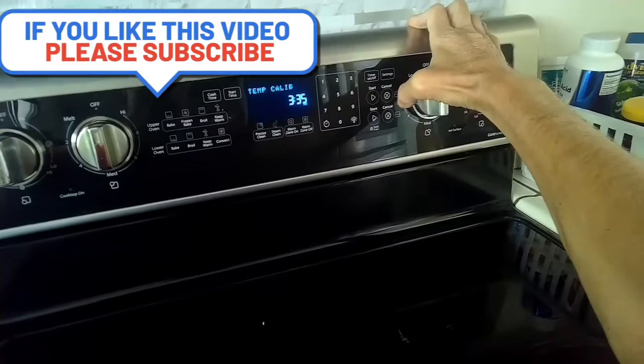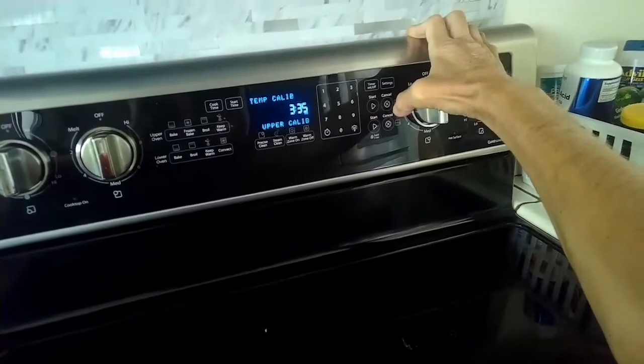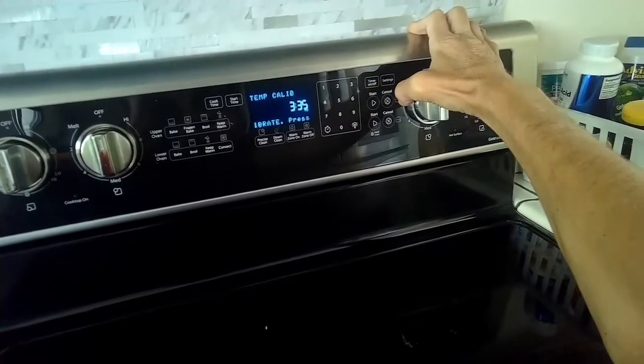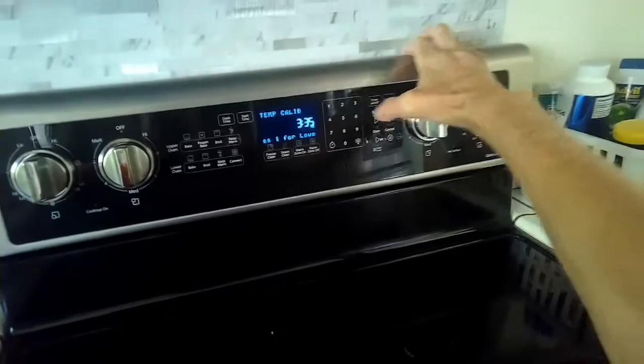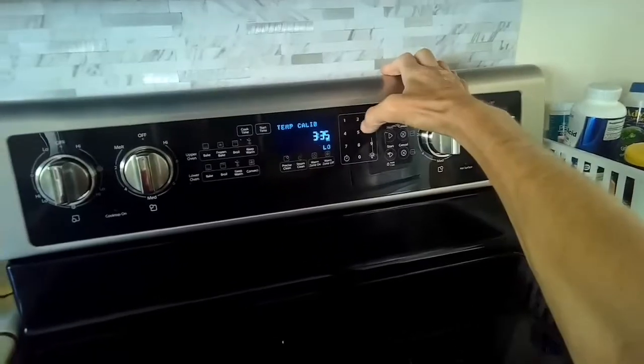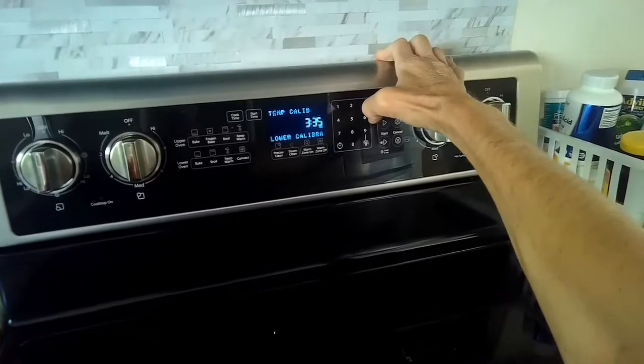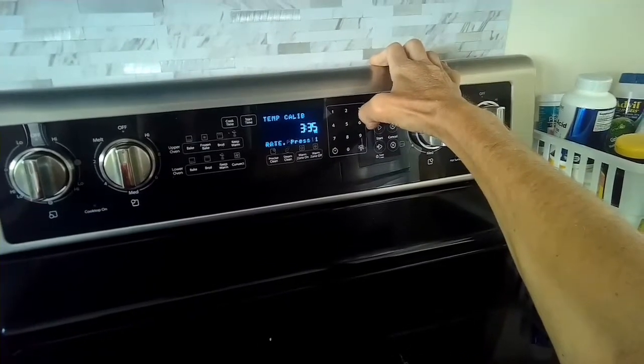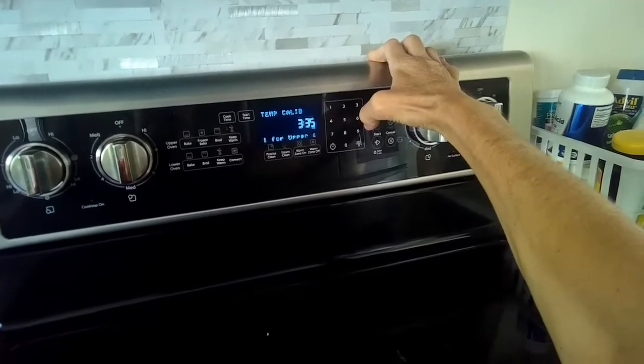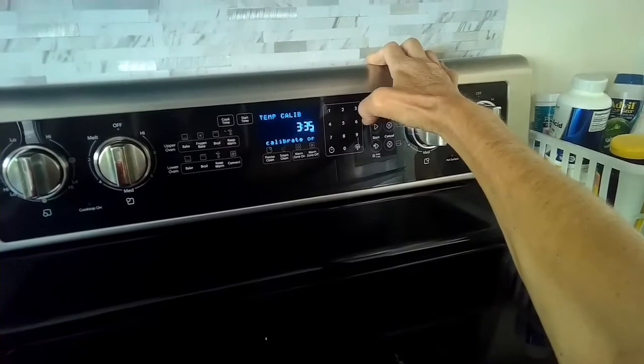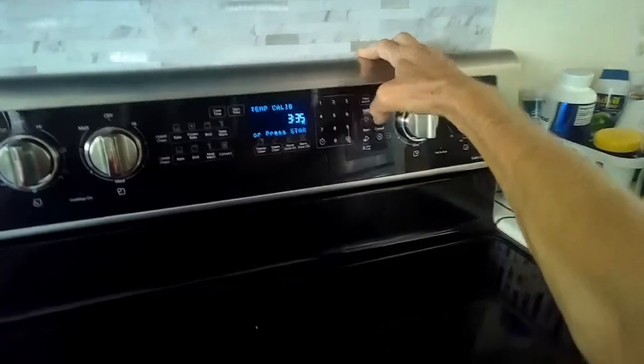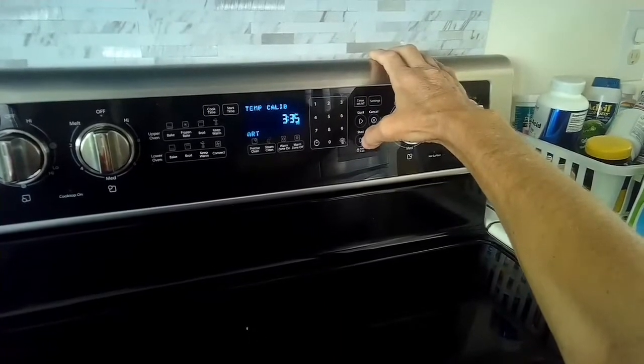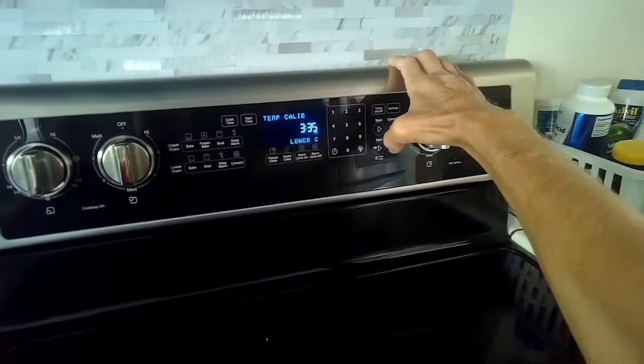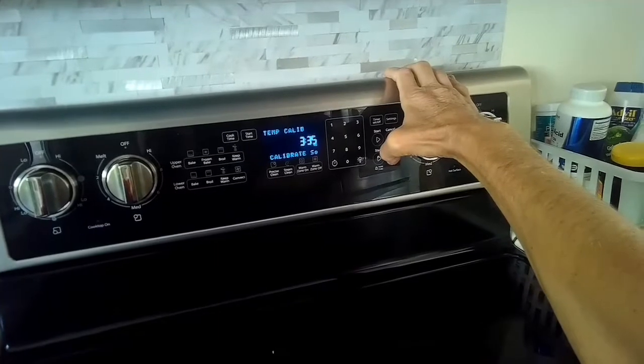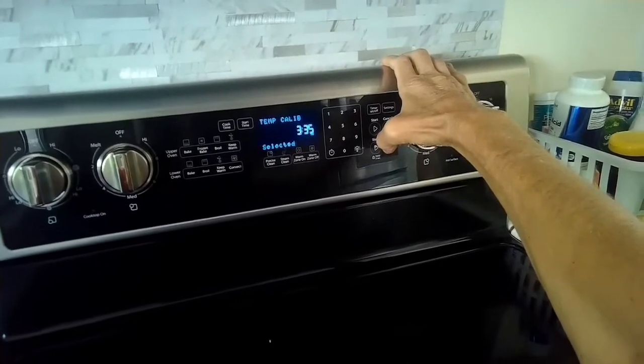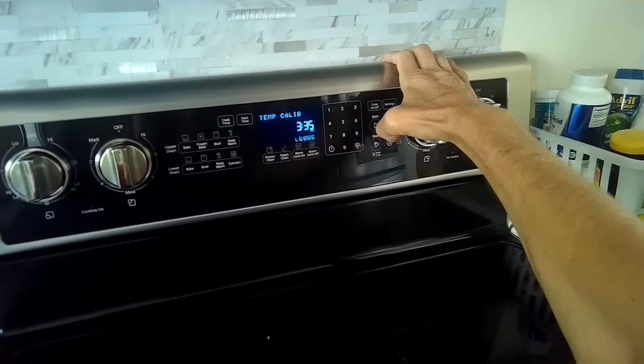So press 1 for lower calibration, or press start. Okay, we want lower, so we're going to press 1. Temperature calibration. Okay, lower calibrate, press 1 for upper. Okay, we want 1. Or press start. Okay, we're going to press start. Lower calibrate, selected. Okay, good. Let's see what it does now.